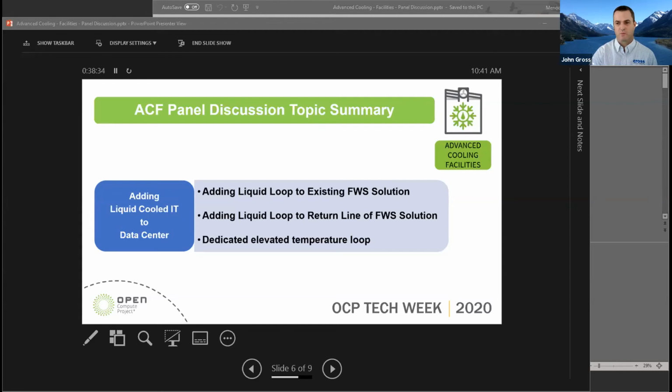And I did some work a couple of years ago with some two-phase immersion. We actually had a client ask us not how hot can you run two-phase, but how cold can you run it, because they were trying to overclock their IT as hard as they possibly could, which puts that much more stress on that chip case heat exchanger.